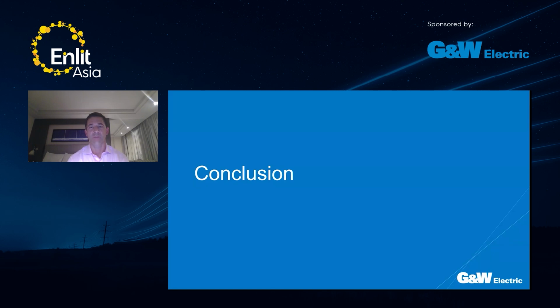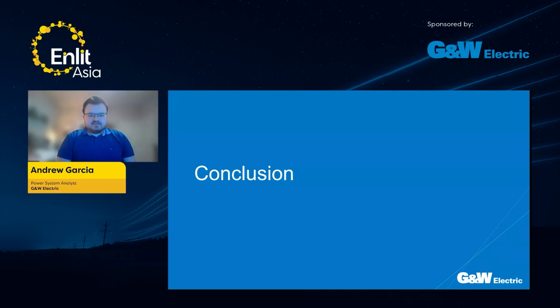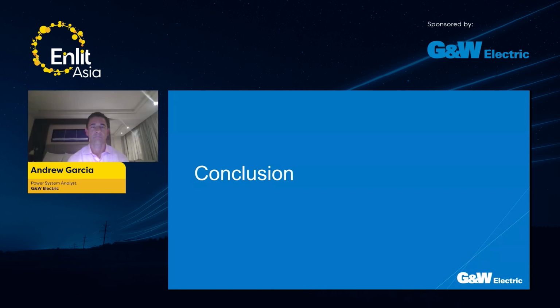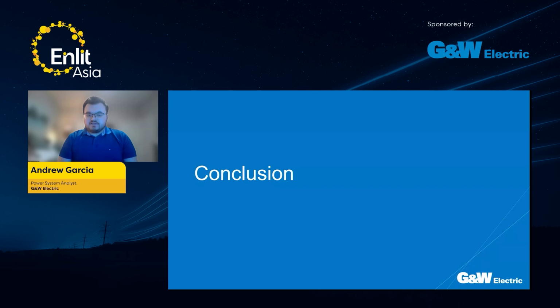So we've talked about distribution level, generally up to 38 kV. Current limiting protectors go up to 38 kV, and as a result they're widely used at distribution level. You could use current limiting fuses at the distribution level. Backup fuses and current limiting fuses are very, very common. Reactors are also a very common device you see at the distribution level. Basically, any of these devices could be used at the distribution level.